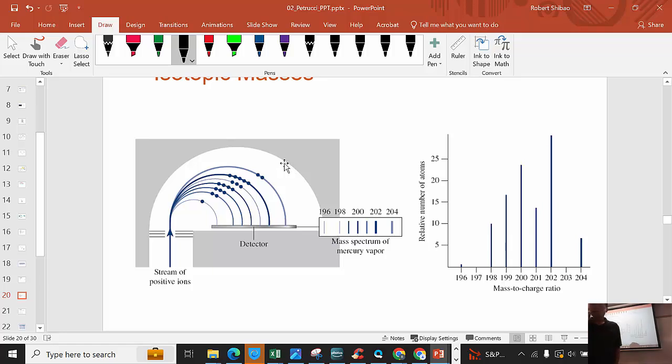Now, the thing is, okay, so they strike here, so how much does that weigh? I don't know how much that weighs. How do we know how much that weighs? So what do we do if we have a balance that isn't reading correctly, or we want to make sure it's going to read correctly? What do we do to balances? We calibrate balances. And when we calibrate balances, we buy a mass, like a kilogram mass.